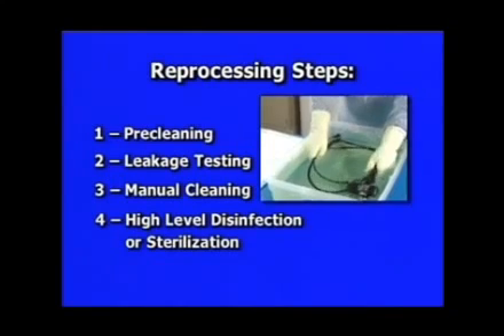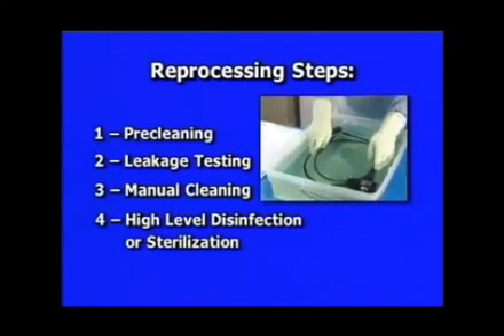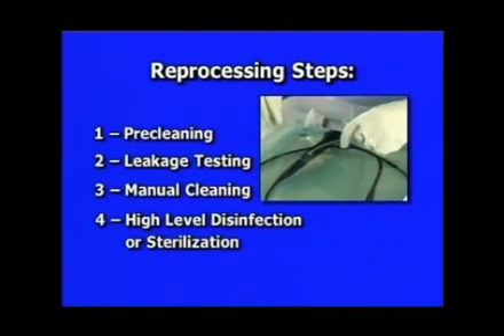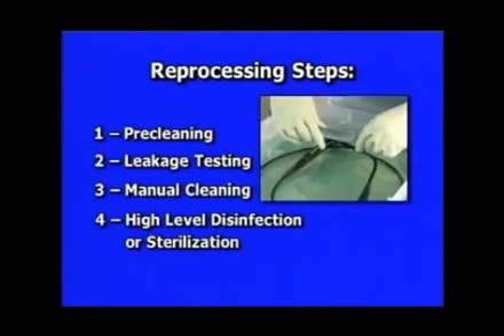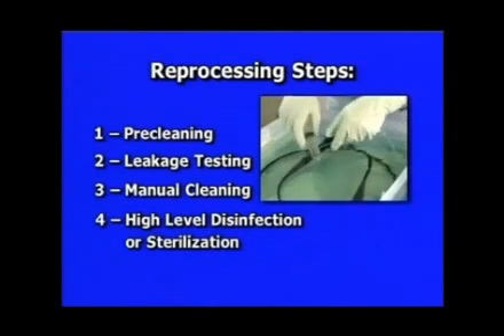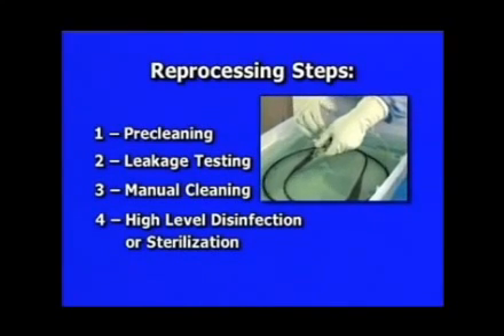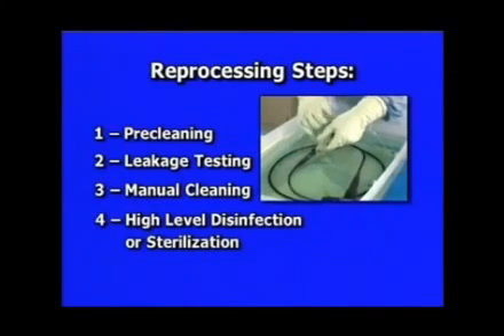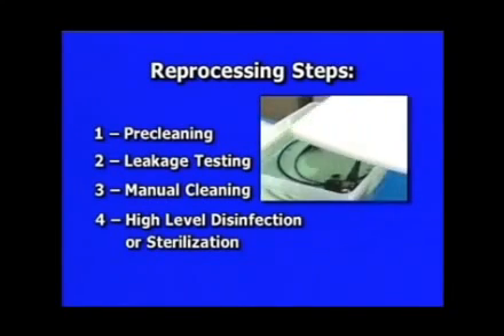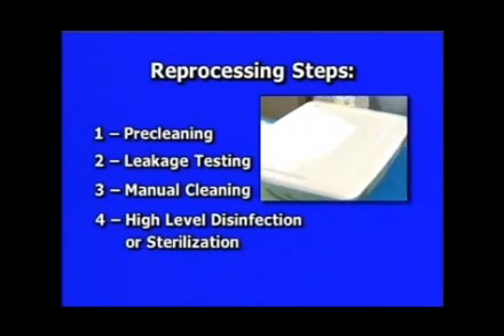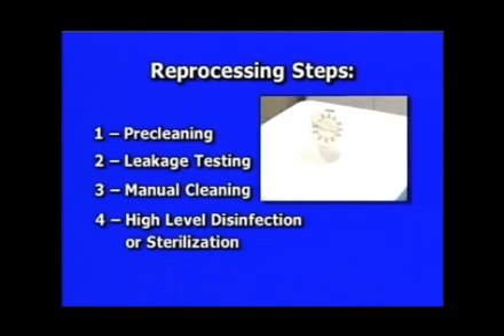High-level disinfection kills or inactivates any remaining vegetative bacteria, viruses, and fungi. The disinfectant should be tested regularly for its minimum effective concentration and used at the temperature and for the contact time recommended by the manufacturer.